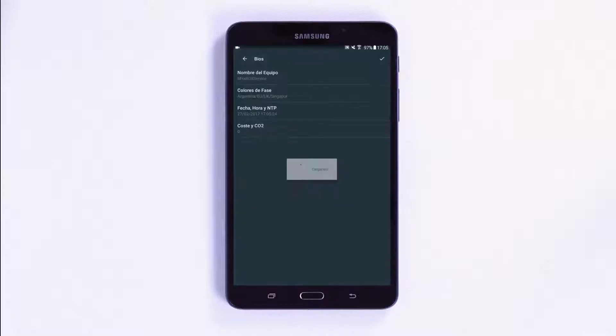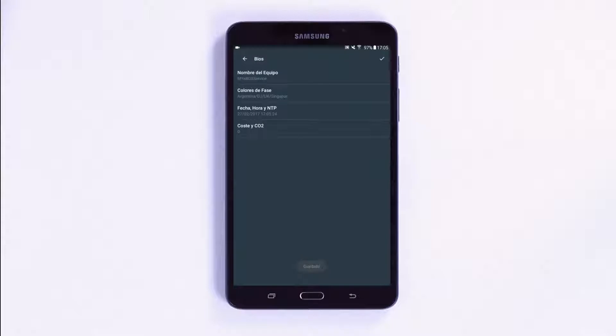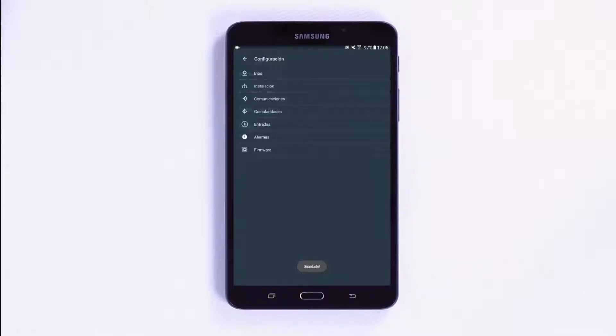Once the configuration is complete, press the confirm button — the tick sign in the top right corner — to save the changes. When you return to the installation menu, you can access the current clamps sub-menu to configure the scale of the various sensors and the phase, neutral and leakage clamps.